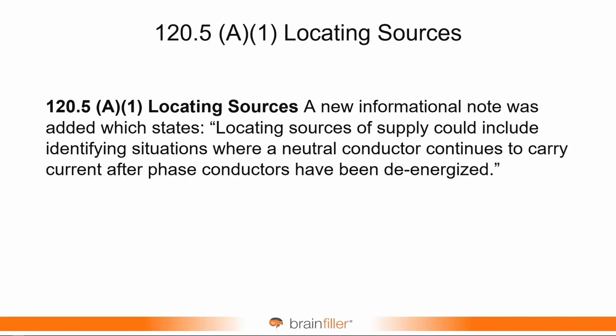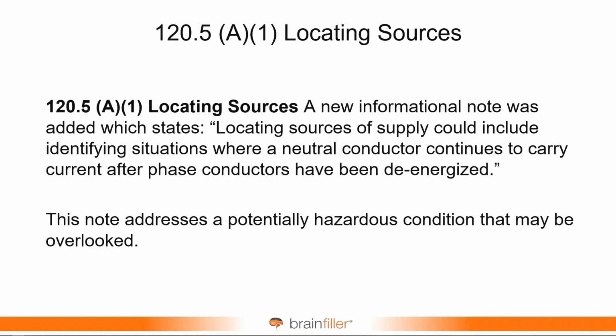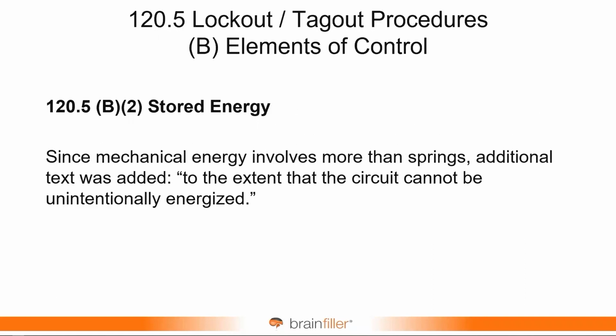120.5(A)(1), locating sources. There's a new informational note that states locating sources of supply could include identifying situations where a neutral conductor continues to carry current after the phase conductors have been de-energized. So this was added just due to a potentially hazardous condition that could be overlooked. As part of lockout/tagout, the stored mechanical energy can involve more than springs, so there was additional text that was added.